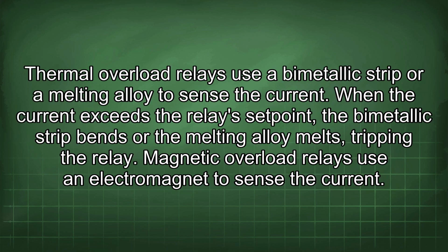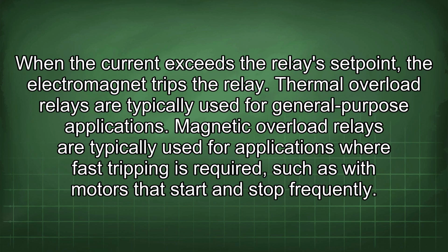Thermal overload relays use a bimetallic strip or a melting alloy to sense the current. When the current exceeds the relay set point, the bimetallic strip bends or the melting alloy melts, tripping the relay. Magnetic overload relays use an electromagnet to sense the current. When the current exceeds the relay's set point, the electromagnet trips the relay.